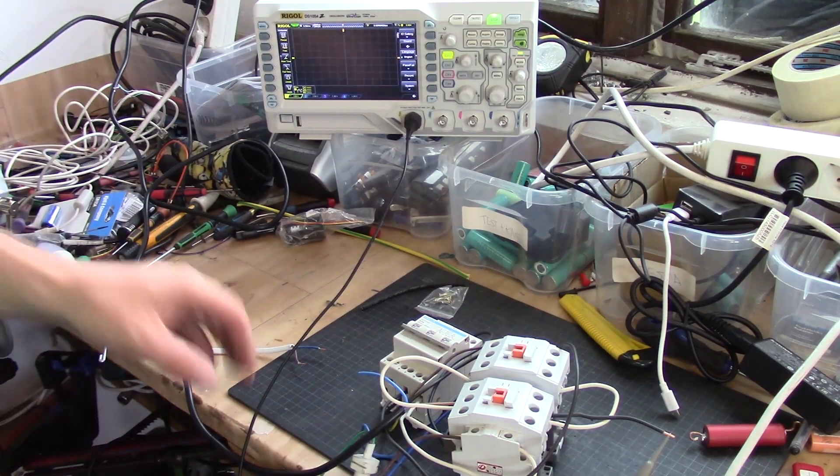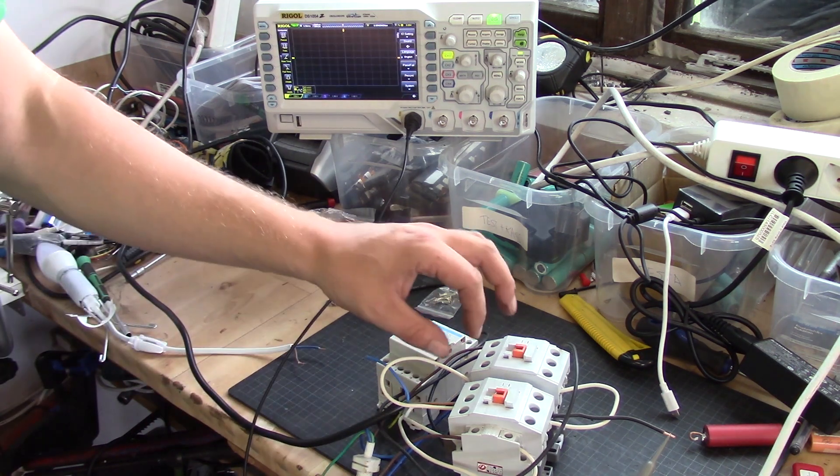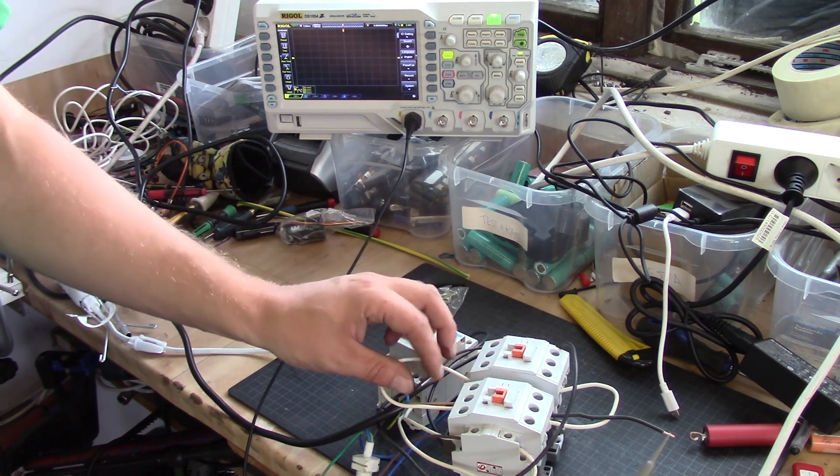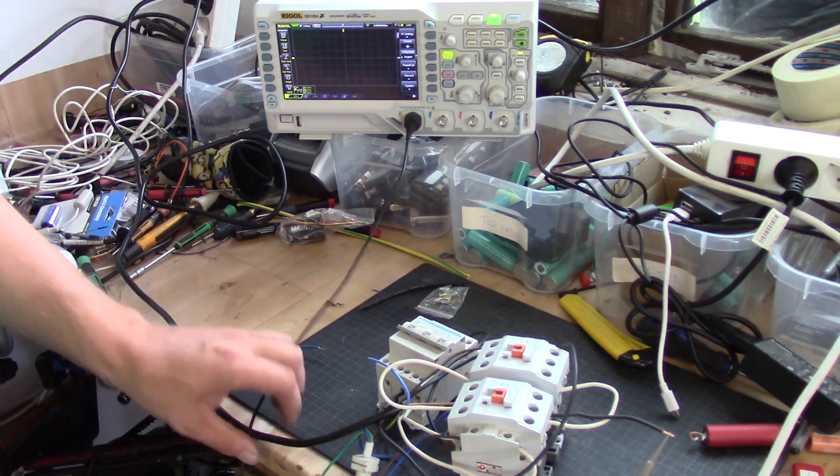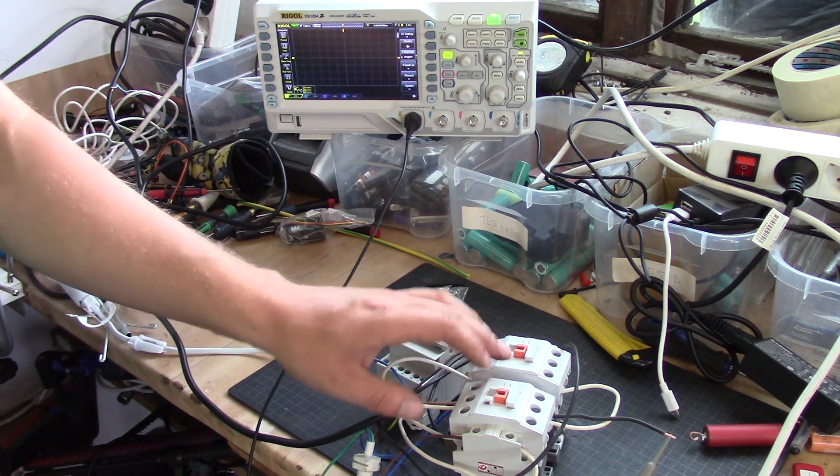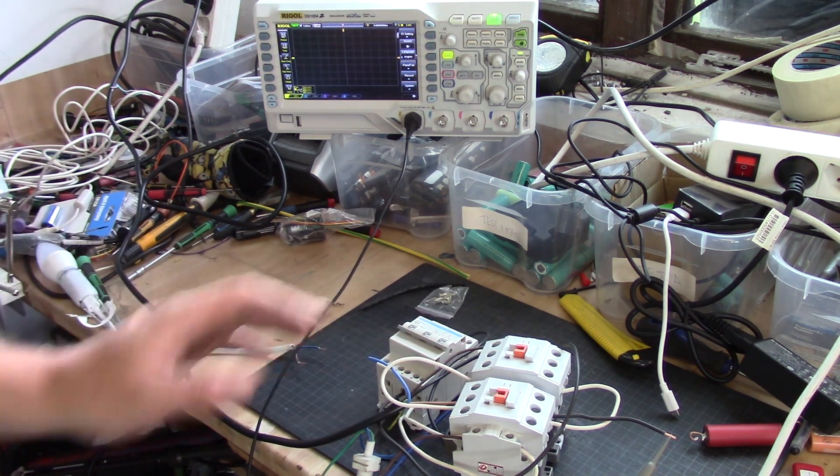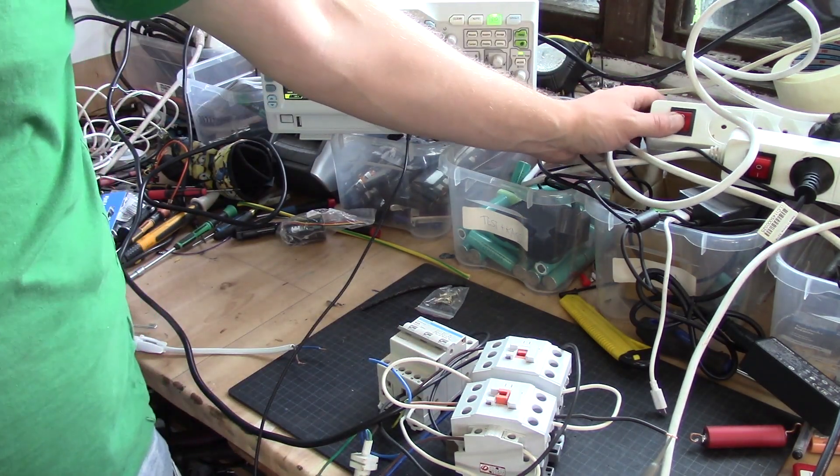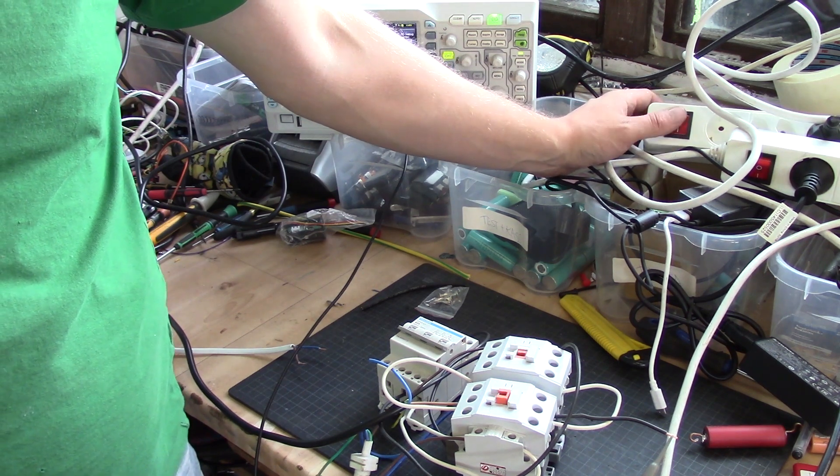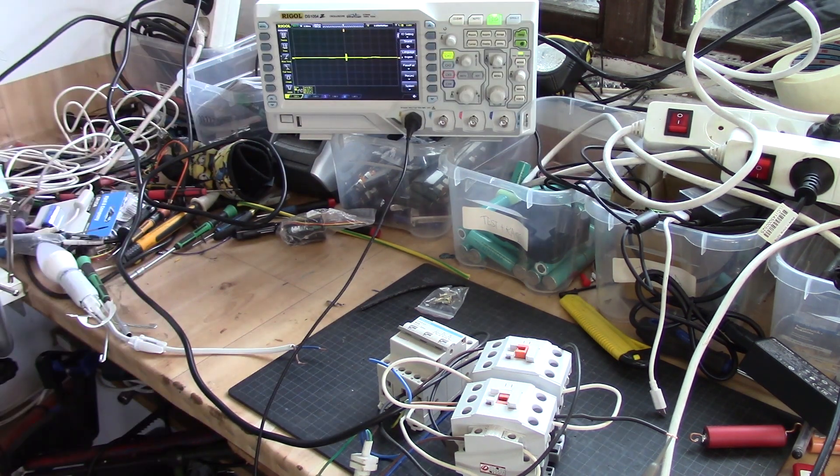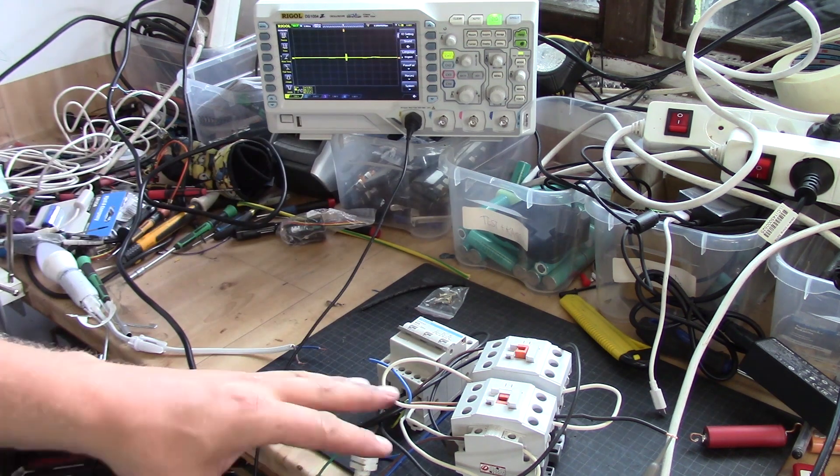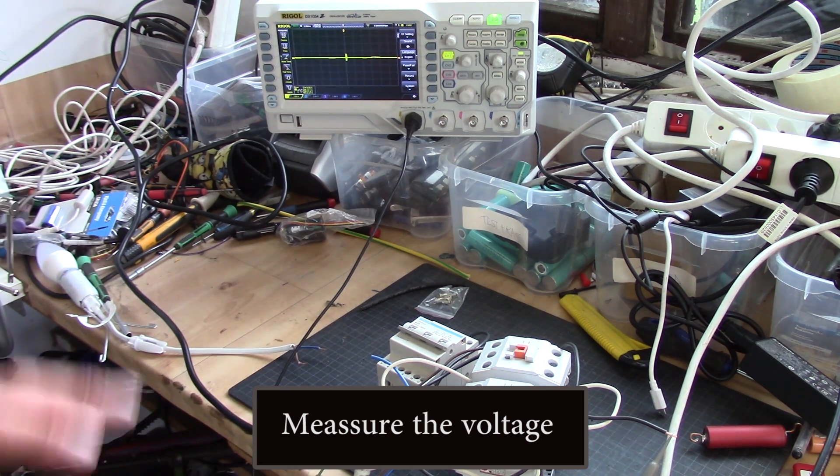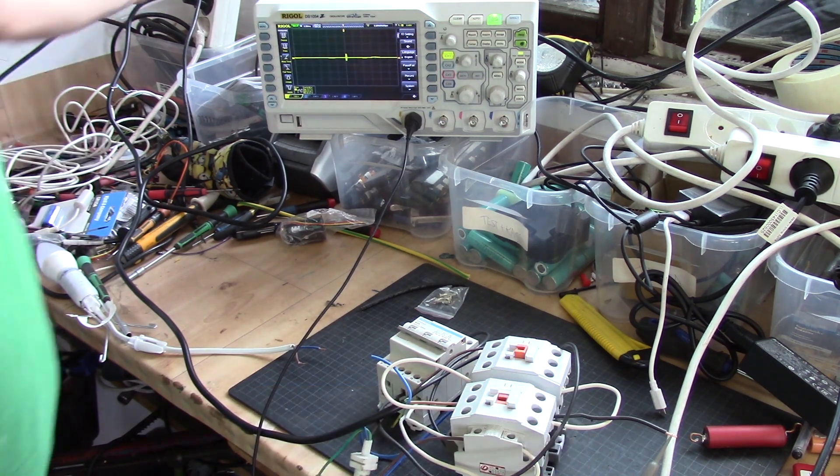First of all, let's take a look at the ATS and see how long time does it take to switch from one to another. The system is hooked up here. I have the input here that I have hooked up to both sides. So what I'm going to measure is how long time are we without the power. So let's hook that up.